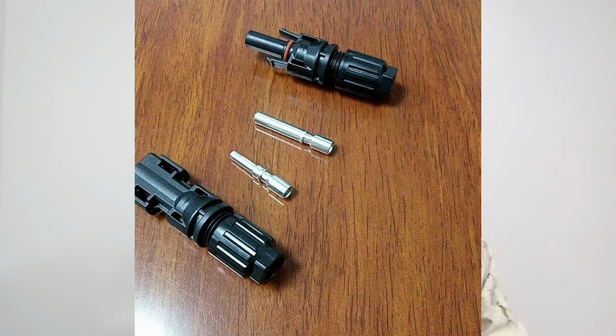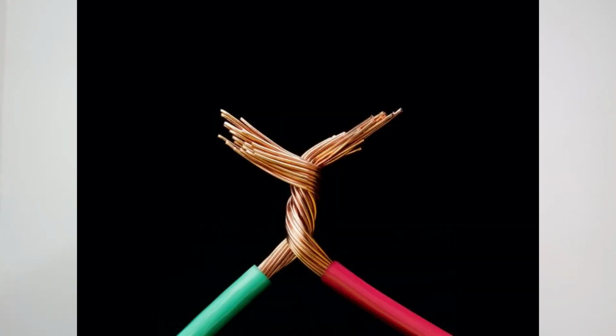MC4 connector is one of the most neglected components of a solar system. It is used for connecting panels together, either in series or in parallel. Most installers usually join solar cables together without using MC4 connector. What happens is that the point of joining with time will begin to heat up due to resistance to the flow of current, which can cause fire outbreak. Therefore, make sure that you use MC4 connector for connecting your solar panels either in series or in parallel to ensure a very firm and waterproof connection.